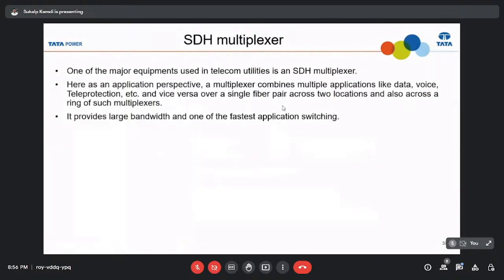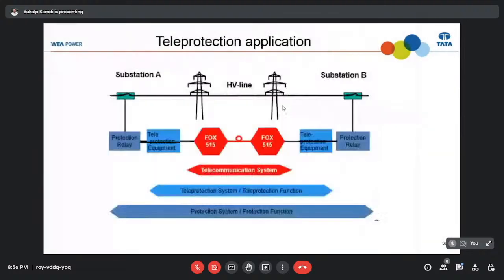The SDH multiplexer I was talking about, here's how the line protection works. The protection relay is connected to my fiber optic terminal equipment, which is my multiplexer, through command cables. Whenever this relay picks up, that binary input goes high, passes through my terminal equipment, and through this fiber optic network it gets communicated within a 7 millisecond time frame, and is able to send the signal.